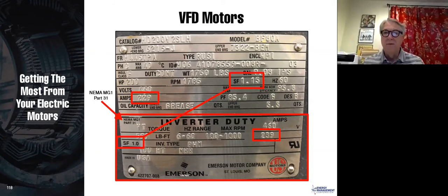Why is that? The reason is that if you're putting it on a drive, you pretty much know that you're not going to be running at full speed. Now, that may or may not be 100% true, but the fact is most drives are going to run somewhat slower. As they run slower, the cooling fan on the motor is going to run slower, therefore you're going to get less cooling. And so we use up the service factor to compensate for the fact that as we slow down, we get less cooling.